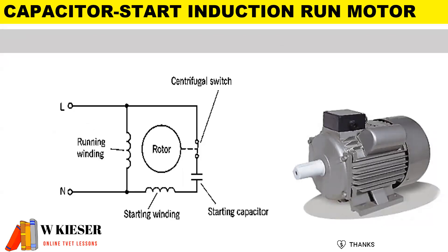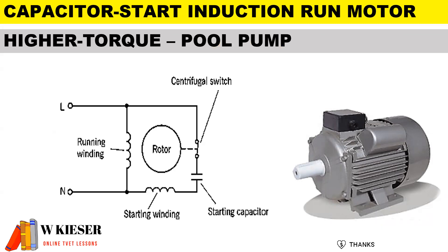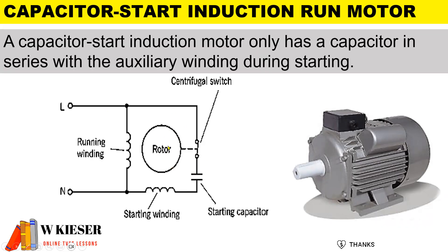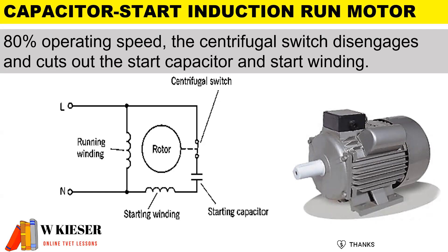In this illustration, we have a capacitor start induction run motor. This motor is mainly used for swimming pool pumps and has slightly higher torque. Looking at the circuit diagram, you'll notice a start capacitor, a start winding, a run winding, a centrifugal switch, and a rotor. In terms of operation, the capacitor is in series with the auxiliary winding only during starting. At around 80% operating speed, the centrifugal switch disengages and cuts out the start capacitor and start winding.